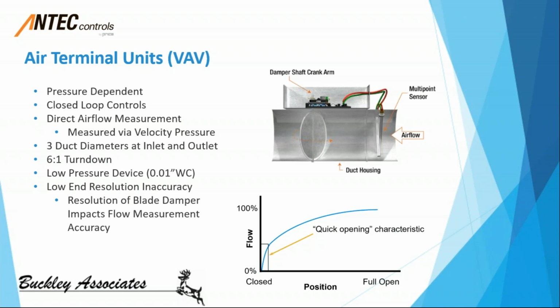However, no matter how accurate the device is, there's an inherent problem at low airflows through this device. Okay, so we have a butterfly damper, and when this damper is very close to being fully closed, at low airflow being allowed through the device, all of our accuracy is lost. If it's just sneaking through, we have very low control over how much air we're allowing through this device. So a VAV box is great for a temperature control application. But if precise airflow delivery is required, like we do in isolation rooms for all healthcare applications, this is probably not the device we're going to want to install specifically for that application.